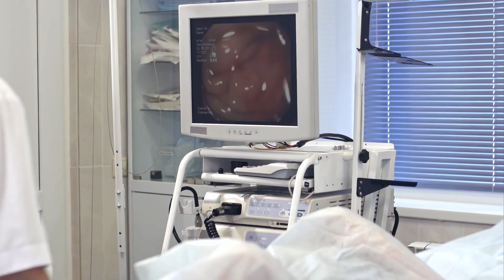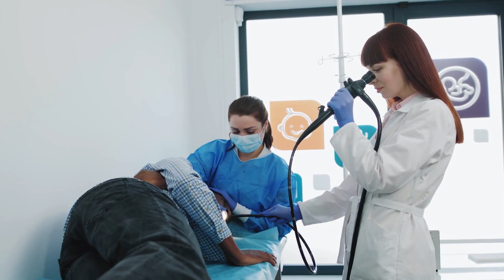One of the problems is that the endoscope is very complex. It has very long and narrow lumens. The interior diameter may be 1 millimeter, and we need to eliminate all 10 billion microorganisms associated with that scope. And we know that more than one survive disinfection, and that's why sterilization and terminal sterilization is preferred for patient safety. For decades, the challenge has been temperature. Traditional methods use high heat, which is effective for metal but destructive to endoscopes.